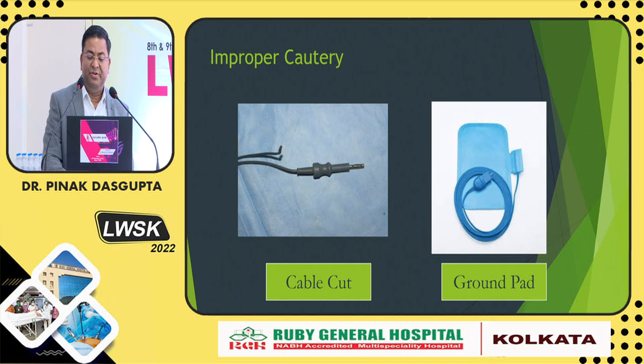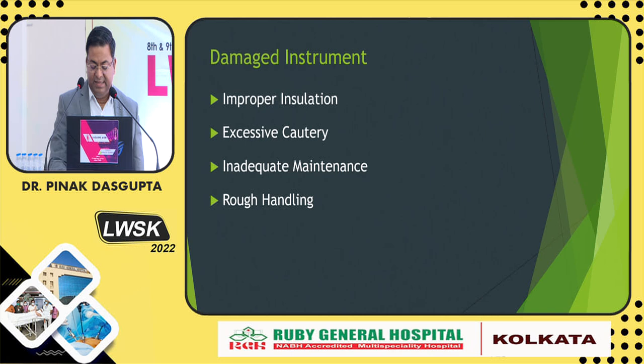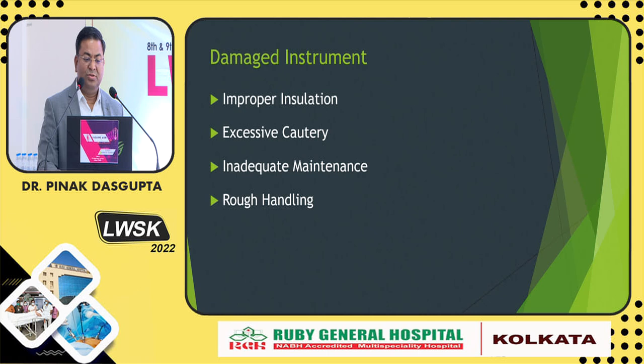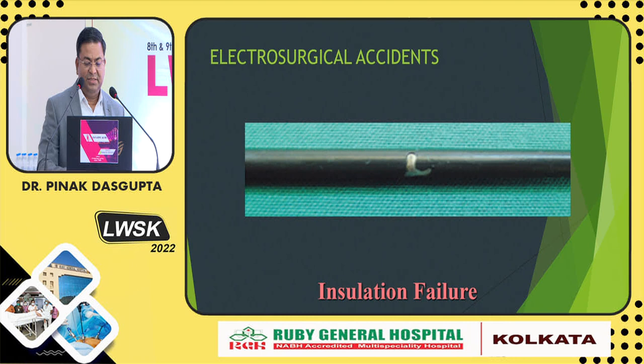So before inserting the instrument, one should also ensure that the laparoscopic instrument is properly insulated and there is no damage to the outer sheath, because insulation failures like this can cause serious damage.